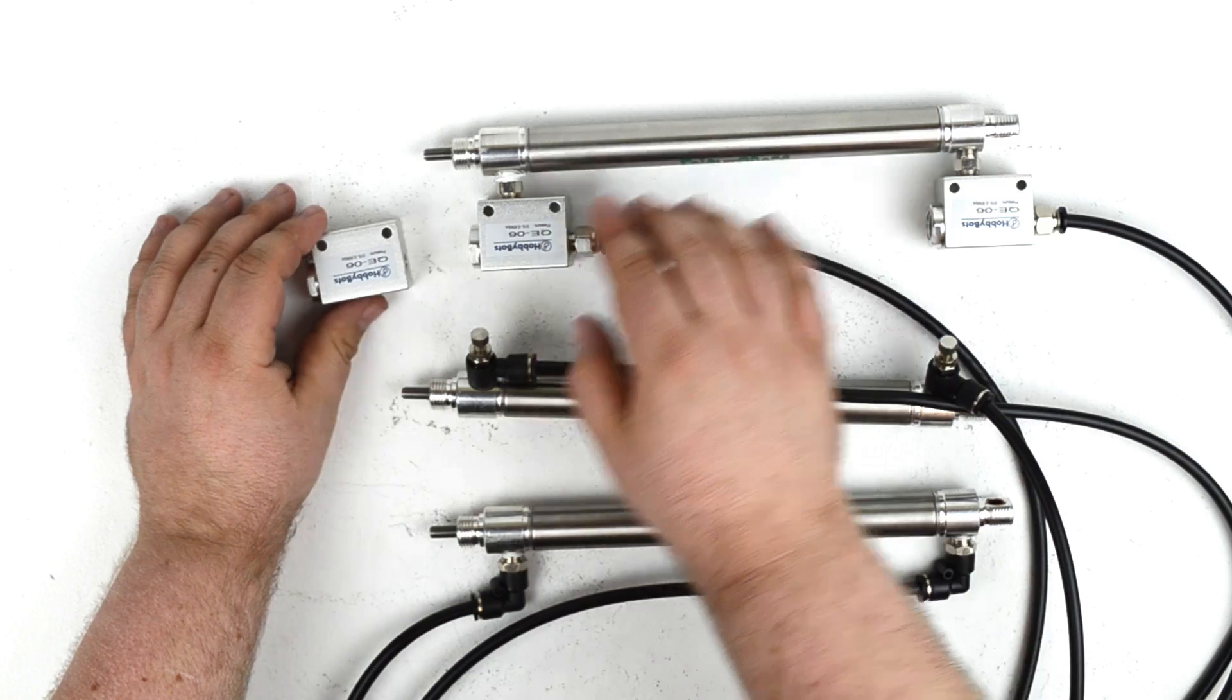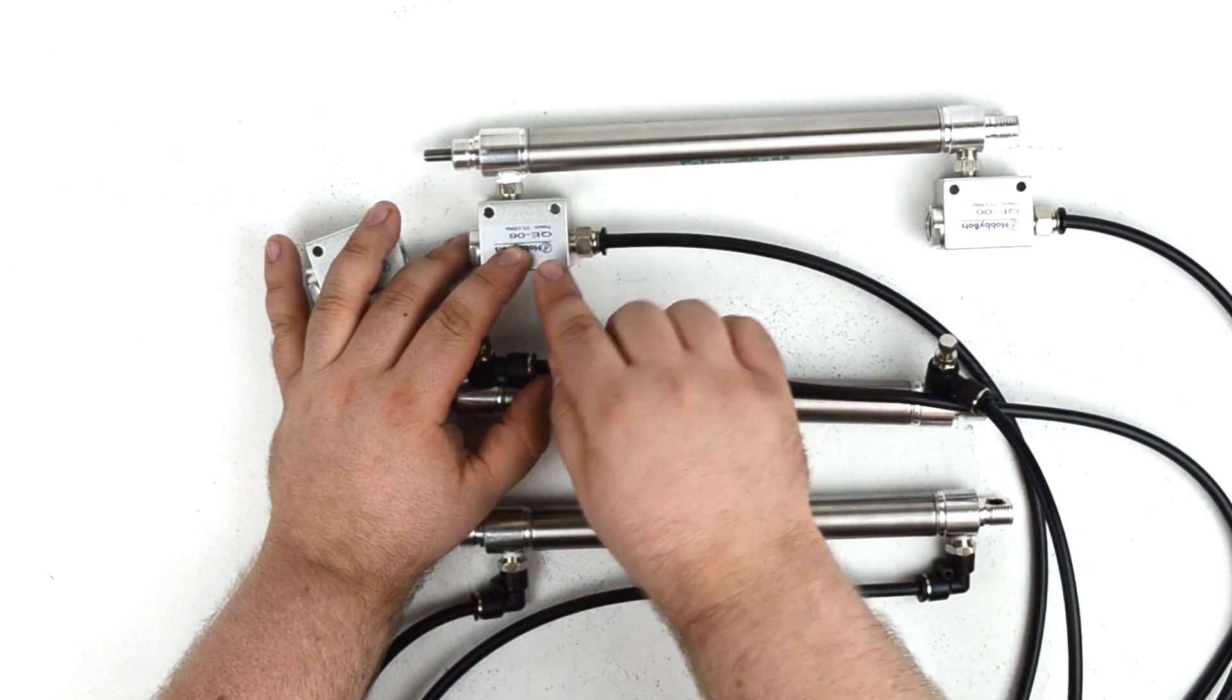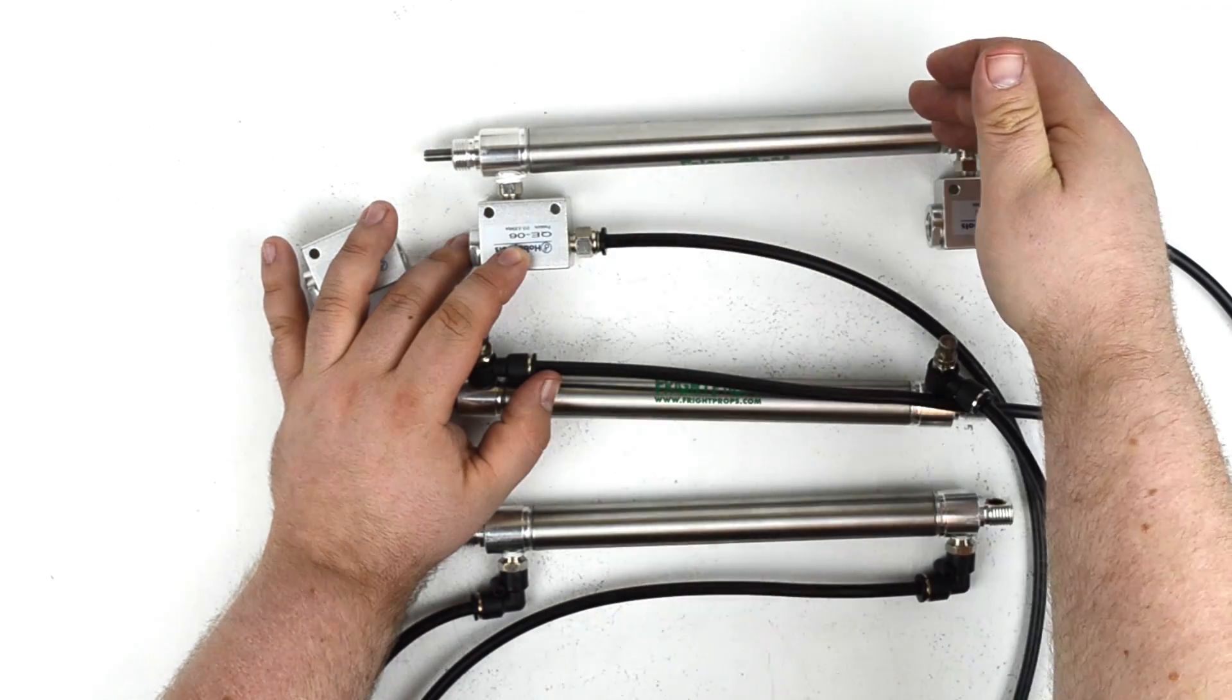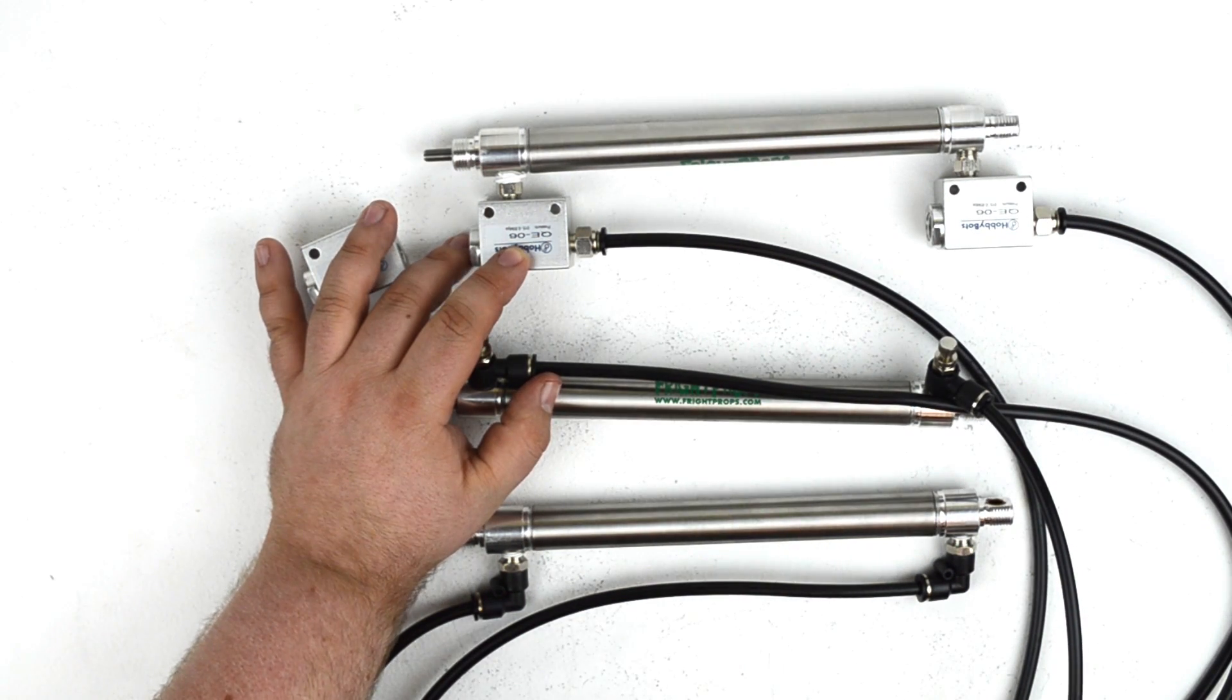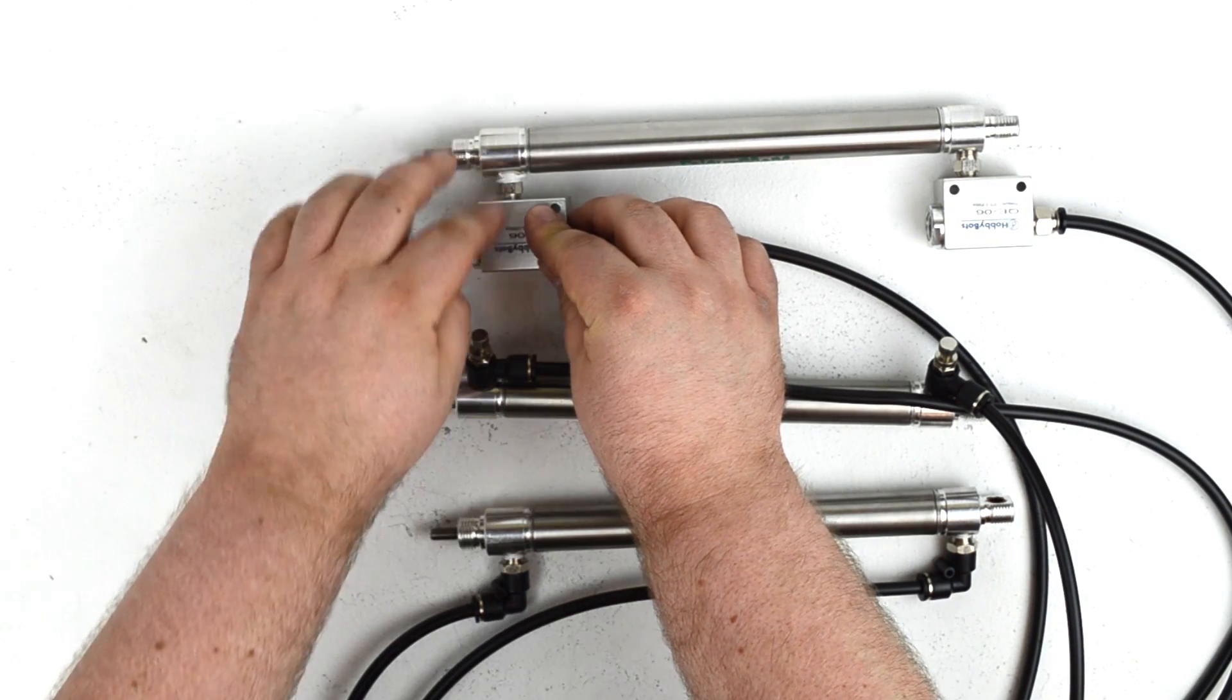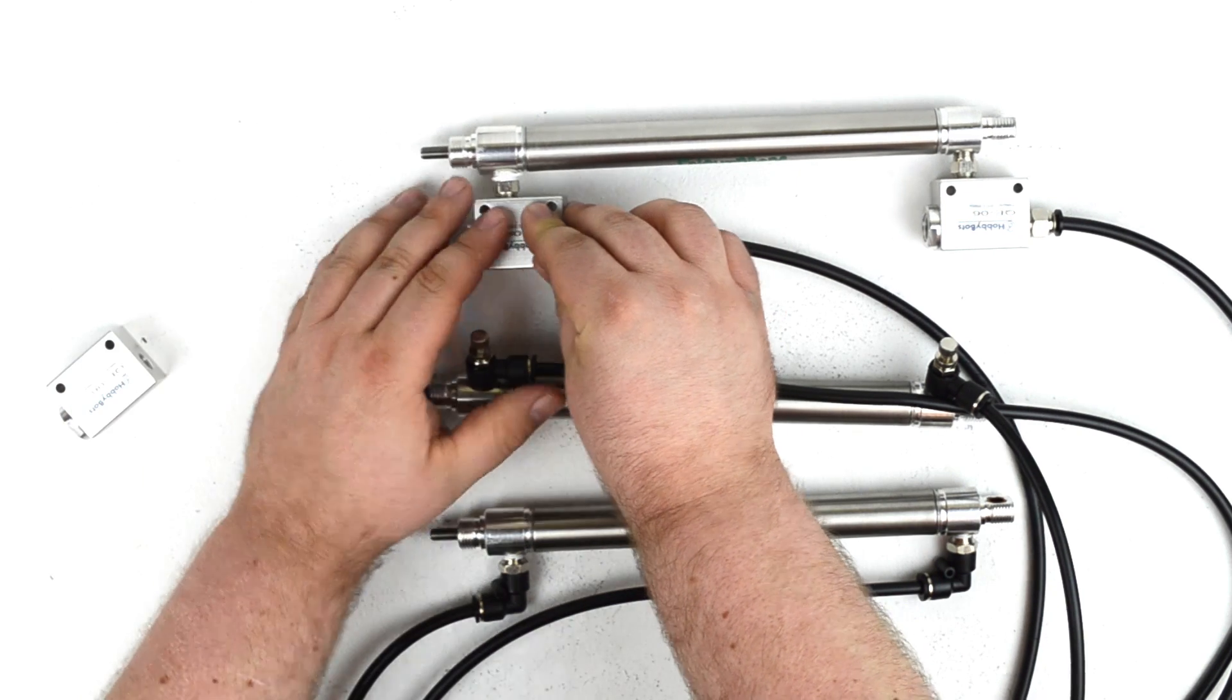Now how this works is that traditionally, when a cylinder receives air from the solenoid, the air comes into the cylinder, pushes the rod out, and then it has to exit again, back down the airline, all the way to the exhaust on the valve. By using a quick exhaust valve, the air is allowed to exhaust directly at the cylinder connection, which makes it much more fast. So let's check that out.